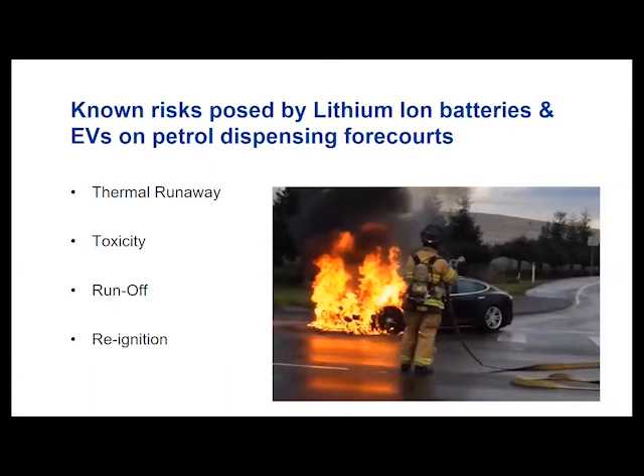Due to the nature of the fire, thermal runaway requires significant cooling, and that currently is done by pouring copious amounts of water onto the fire, which produces a considerable amount of runoff or wastewater from the extinguishing process. So large volumes of water are required to cool the battery, typically in excess of 20,000 litres for a medium-sized electric vehicle. A consideration is that on a forecourt, this has the potential to overwhelm the drainage systems. The runoff would also be mixed in with toxic compounds, so it could also represent a risk to the environment if not properly contained.